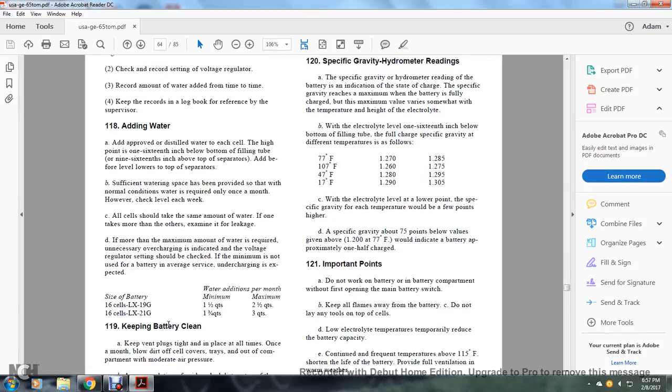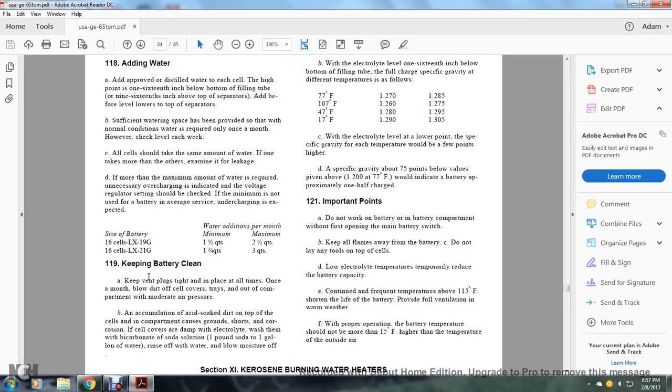Service battery specifications: 16-cell LX-19G water addition per month, minimum 1 1/2 quarts, maximum 2 1/2 quarts. 16-cell LX-21G water addition per month, minimum 1 3/4 quarts, maximum 3 quarts. Keep the battery clean.